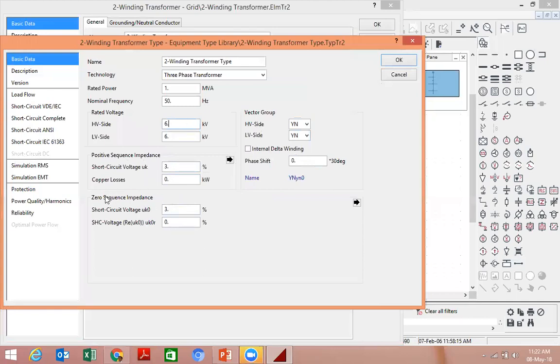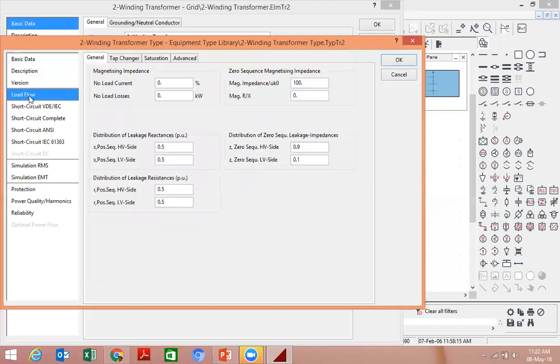Same for the zero sequence impedance. And in the load flow, we can also specify no load current, no load losses, and magnitude R by X ratios. These are some of the advanced things. I haven't used these yet, like distribution of leakage reactance in per unit, but you can specify them to make your calculation more clear and more accurate.